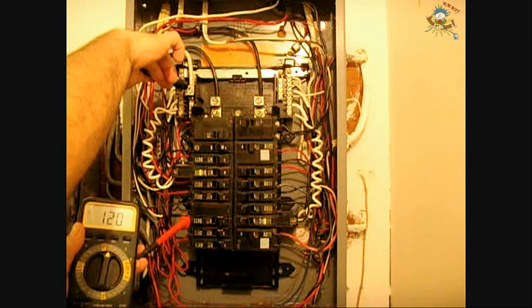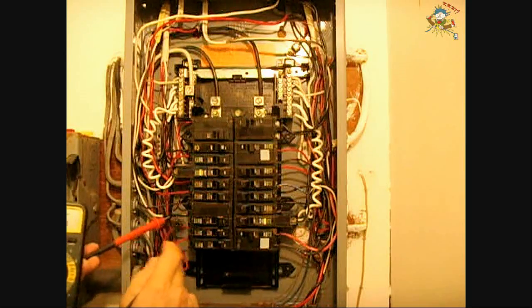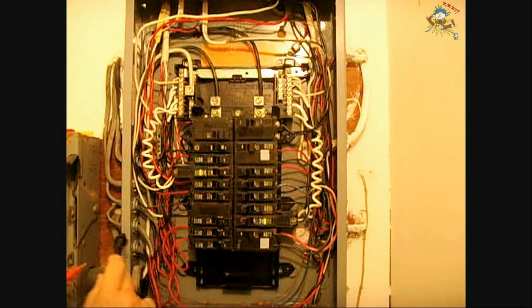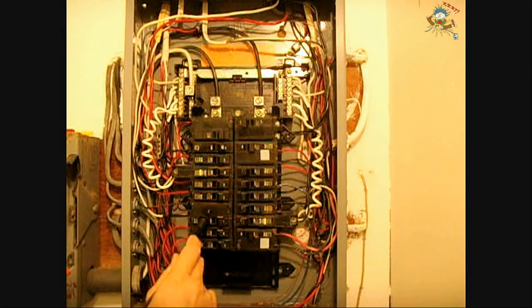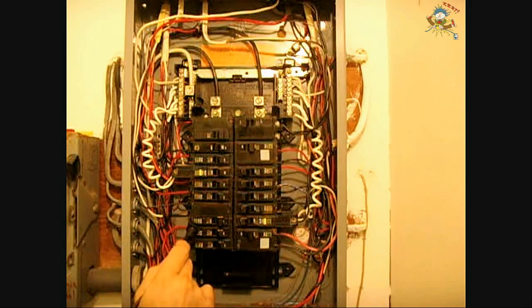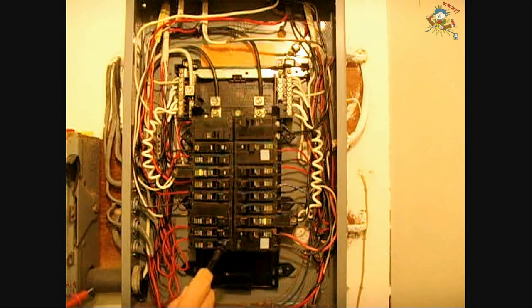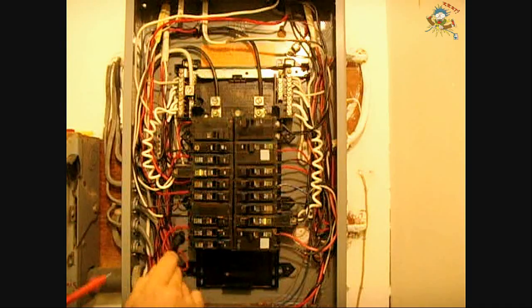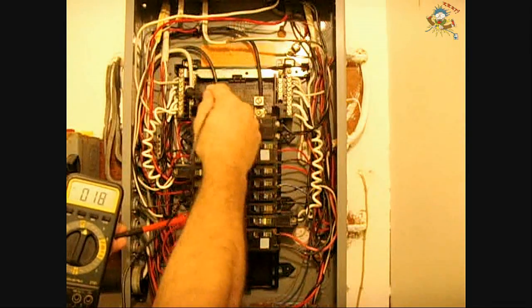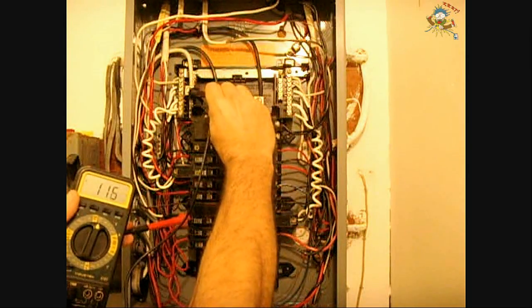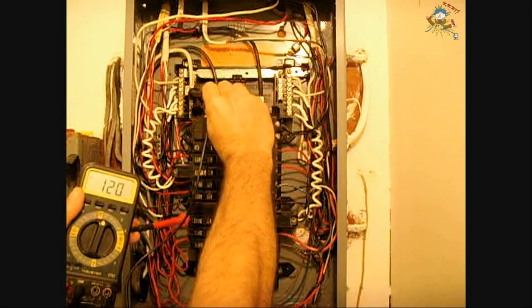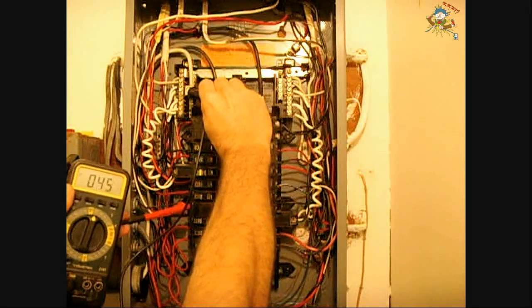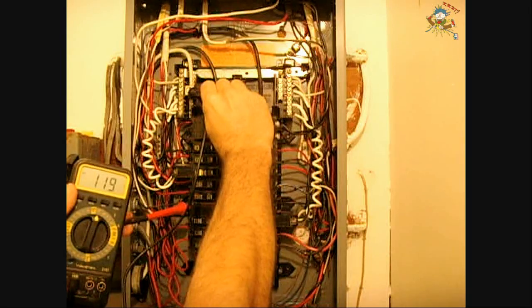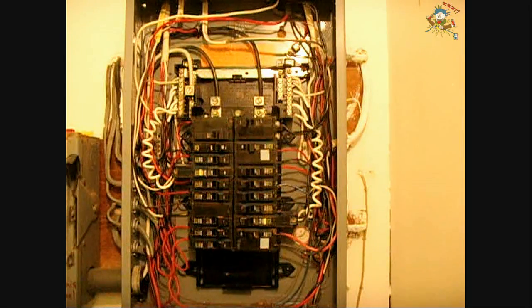So I got 120. Because if you do that and there's a problem with the breaker, you're going to have a loop back. So the one leg will feed through the circuit and come back, and it won't connect to the other bus. So you're going to see 120 and 120. So I'll do this, alright? So you see there's 120. And I'll do the one above it. And you'll have 120. That's not how you test a 240 volt breaker.